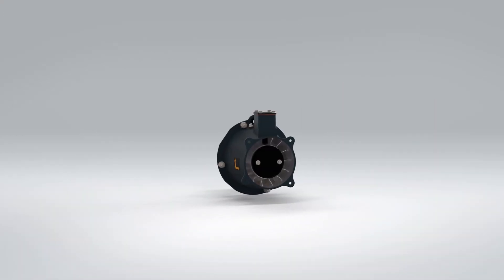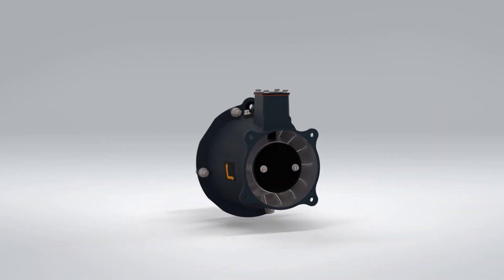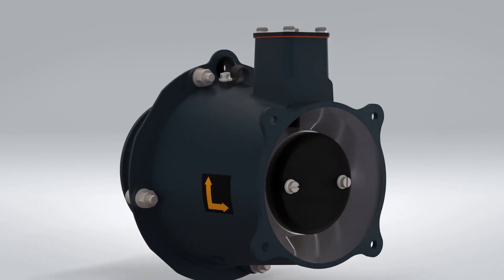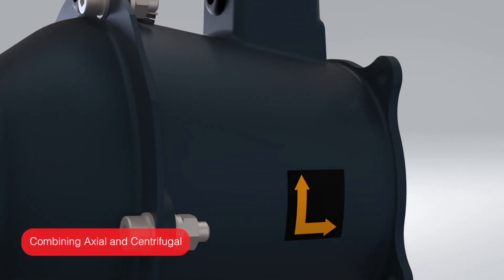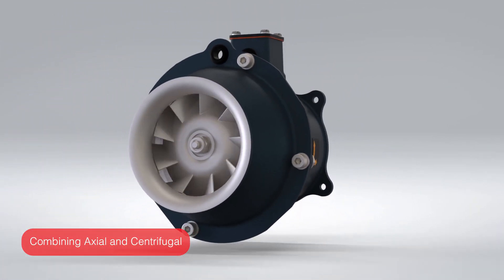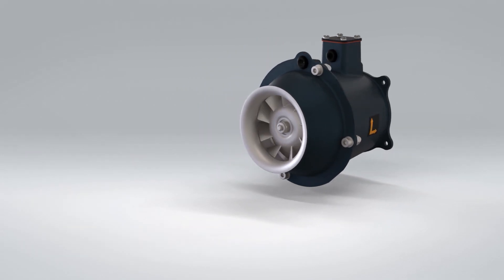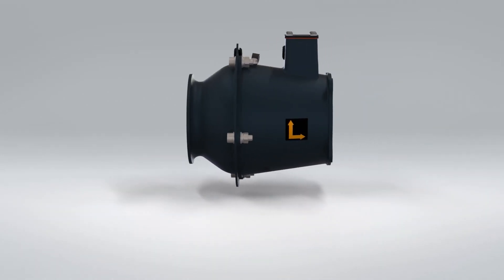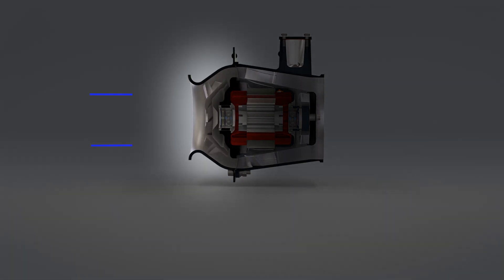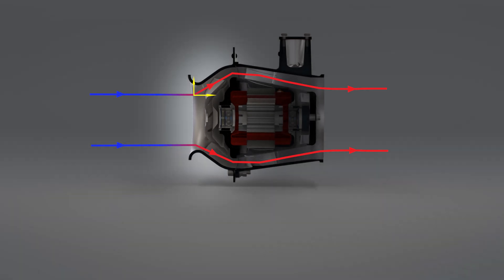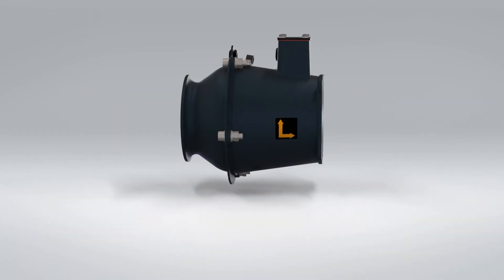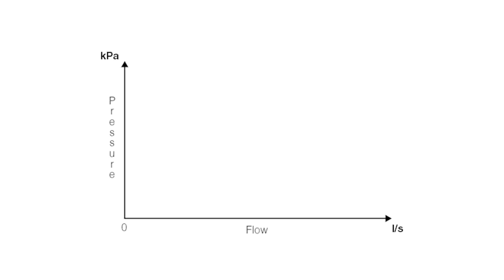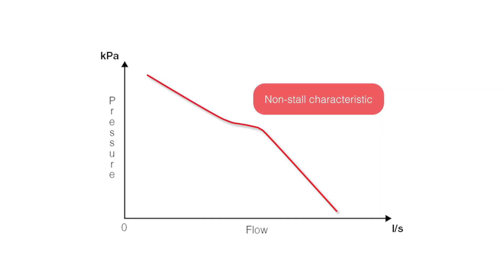That brings us to the mixed-flow fan, and as its name suggests, this type of fan combines elements of an axial fan and a centrifugal fan. The fan uses an efficient aerofoil blade like an axial fan, but wider and arranged around a conical hub. Combining these features generates a flow typical of an aerofoil blade, but forcing the air to flow past the cone introduces an axial and radial characteristic to the airflow. The net result is a fan capable of producing high airflow whilst dealing with high pressures caused by upstream airflow restrictions.